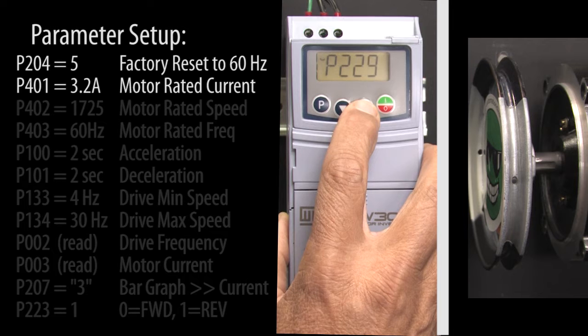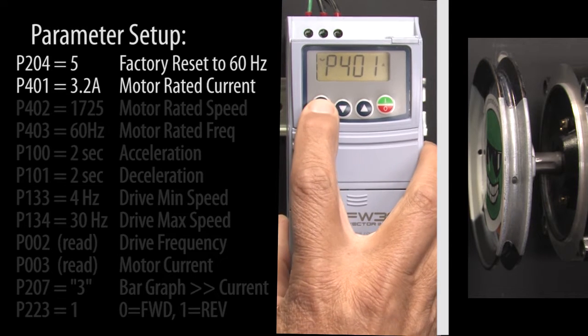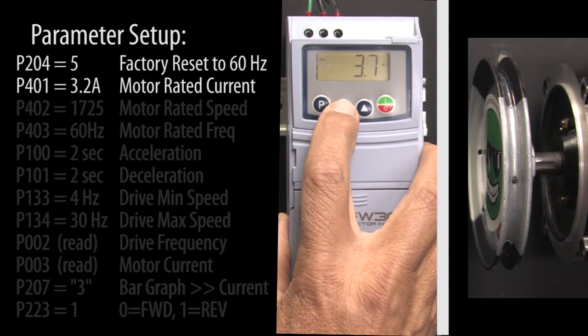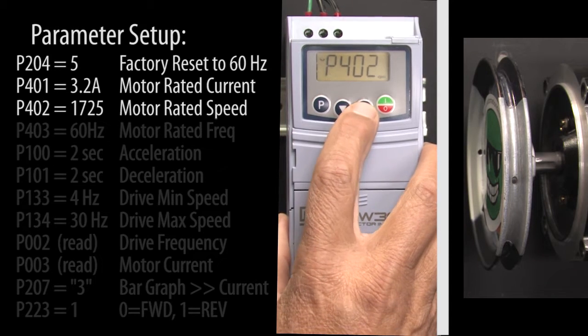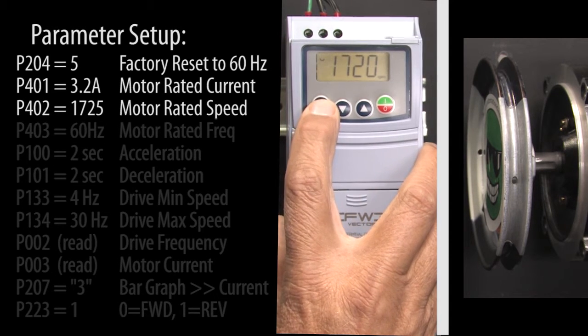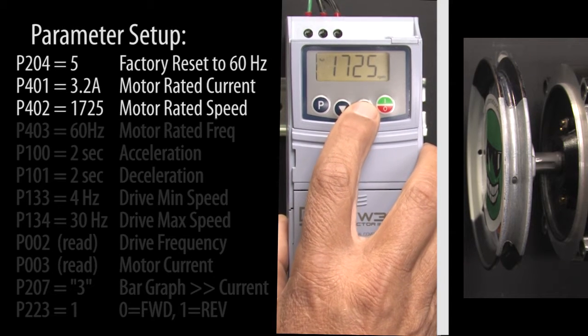Scroll to parameter 401 which is the motor's rated current. Ours is 3.2 amps so we enter that and press P to accept it. Parameter 402 is the motor's rated speed, we'll modify that to 1725 and hit P to accept that.